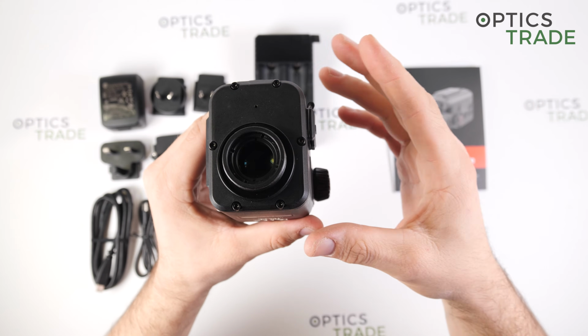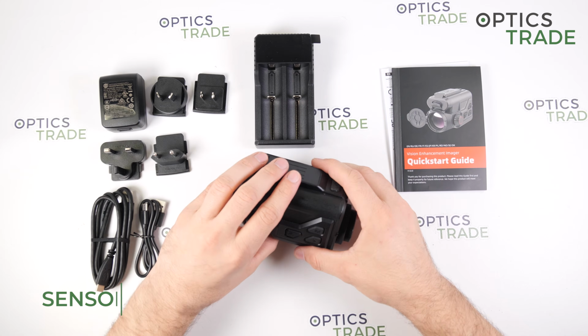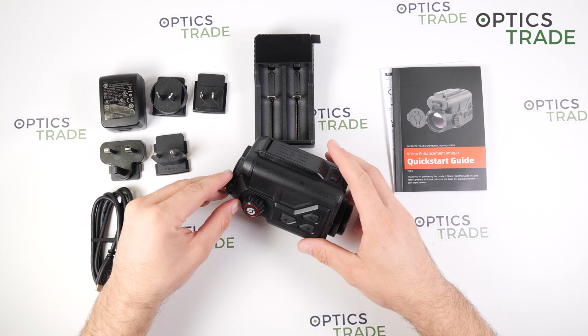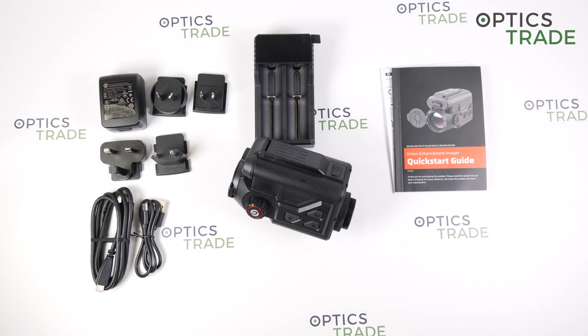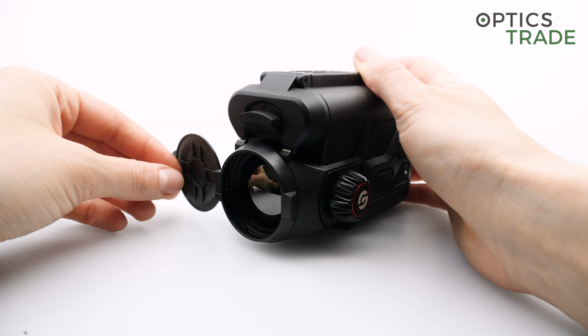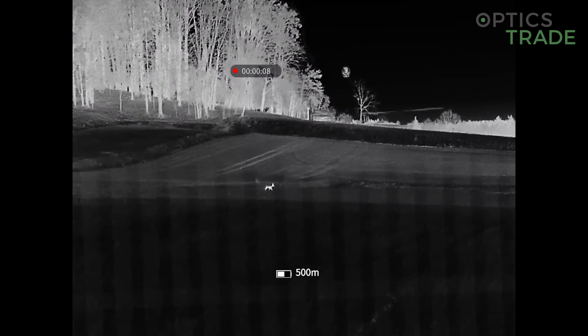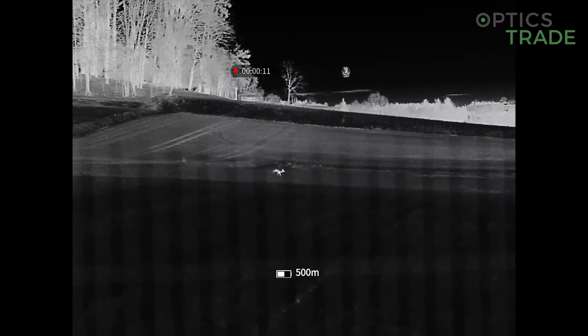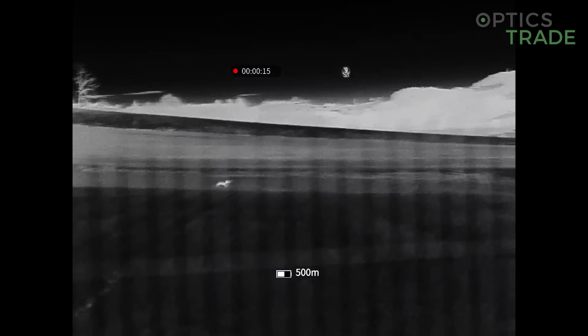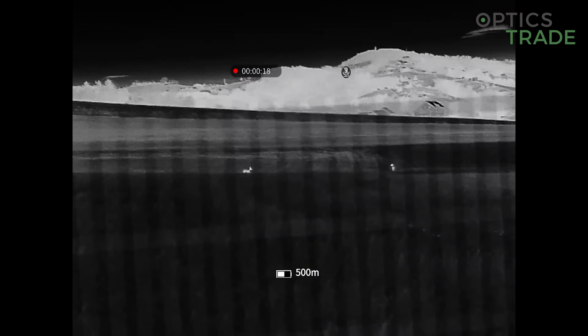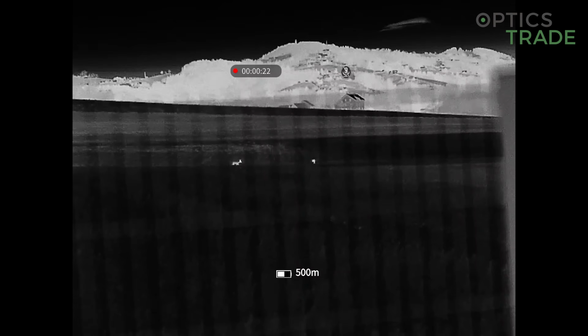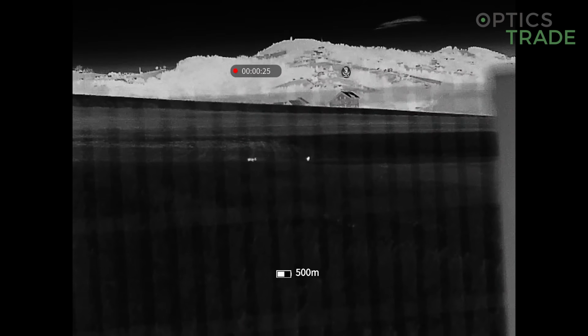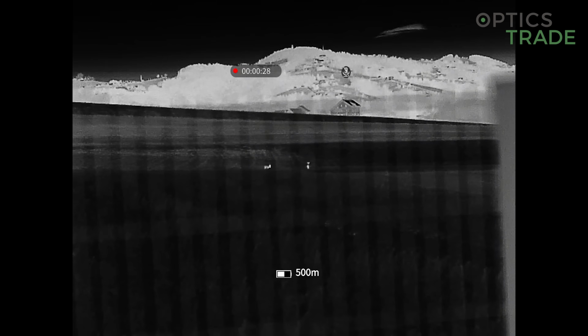Now for the sensor specification, built in is a Vox detector with 640 by 480 pixels, and the pixel pitch is 12 microns, so a very small pixel pitch, and the refresh rate of the sensor is 50 Hertz, so you have a really smooth image also on targets which are in motion. The NETD, or noise equivalent temperature difference, is 20 millikelvins or less, so it is very sensitive and you will see very small differences in temperature.